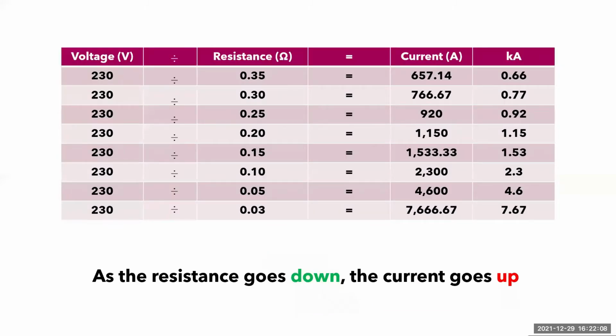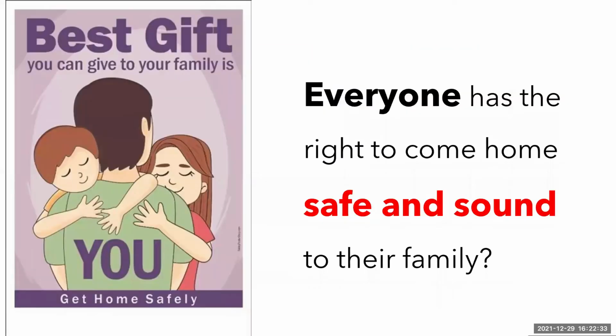In this table, you can see that when the resistance goes down, the current goes up, exactly like you were taught at college. As the resistance starts to drop below 0.15 ohms, you can really see that current jump exponentially. Effectively, the closer we are to the local transformer, the lower the resistance in the supply cable and the higher the fault current available. Now, the question you have to ask yourself is, do I want myself, or anyone else for that matter, to be connected to that amount of current? And hopefully the answer is a firm no.